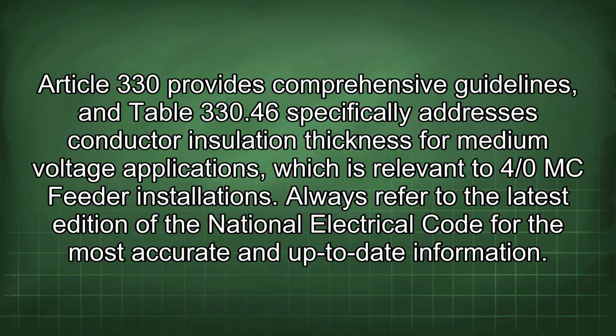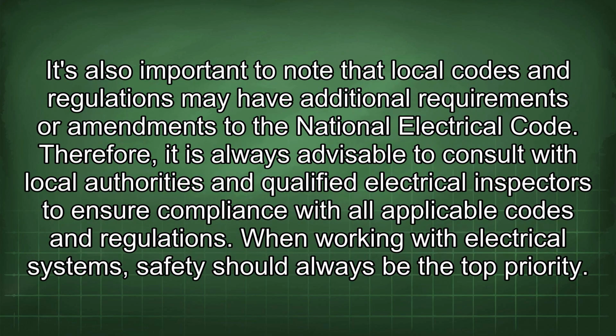or later. Article 330 provides comprehensive guidelines, and Table 330.46 specifically addresses conductor insulation thickness for medium voltage applications, which is relevant to 4/0 MC feeder installations. Always refer to the latest edition of the National Electrical Code for the most accurate and up-to-date information. It's also important to note that local codes and regulations may have additional requirements or amendments to the National Electrical Code.